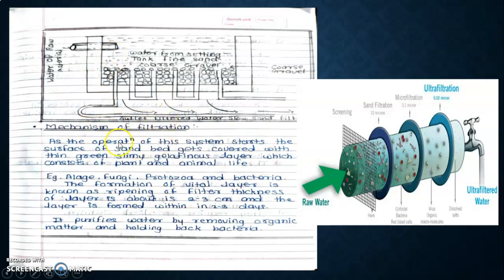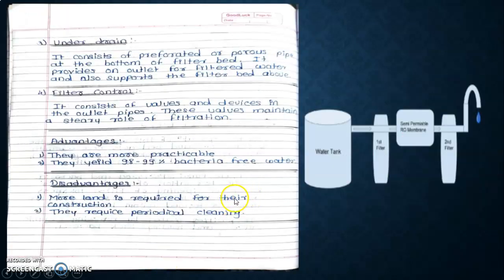Mechanism of filtration: as the operation of this system starts, the surface of sand bed gets covered with green, slimy, gelatinous layer which consists of plant and animal life. Examples include algae, fungi, protozoa, and bacteria. This formation of vital layer is known as ripening of filter. The thickness of layer is about 2 to 3 cm and the layer is formed within 2 to 3 days. It purifies water by removing organic matter and holding back the bacterial spores.